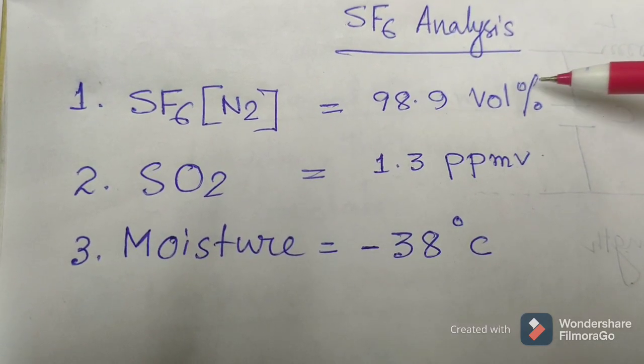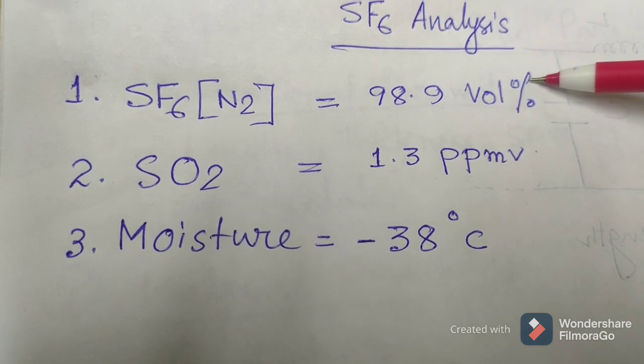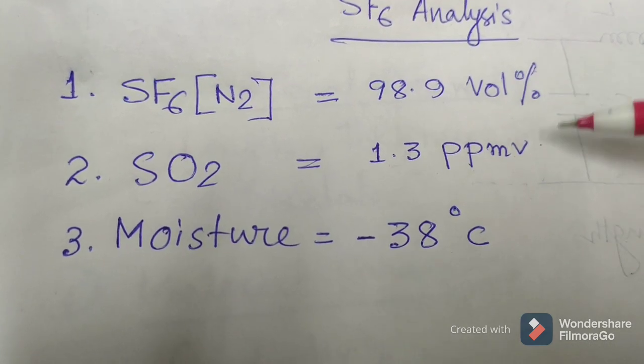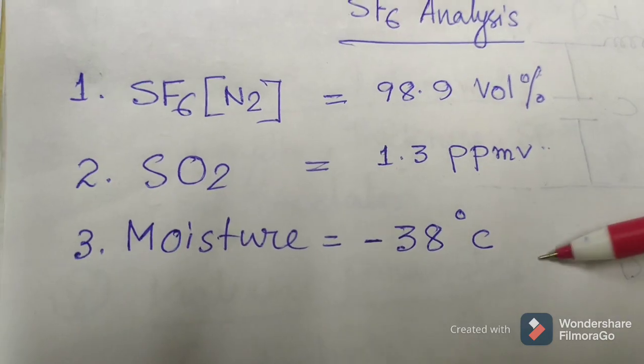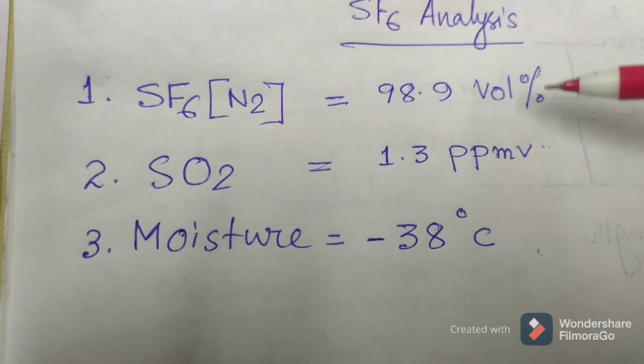The three main parameters are SF6 quantity in percentage volume, SO2 in ppm, and moisture, calculated by the SF6 analysis.